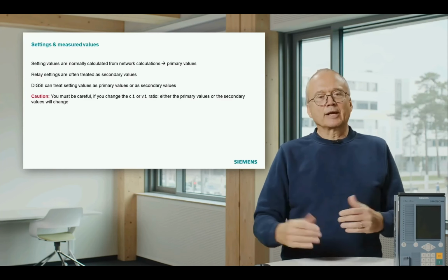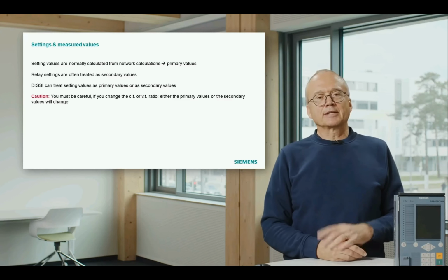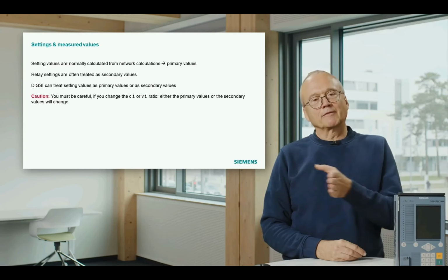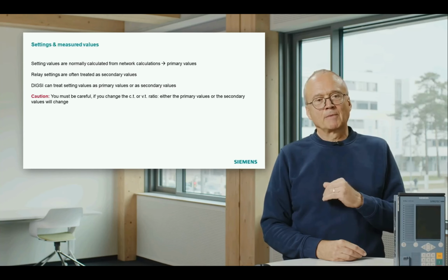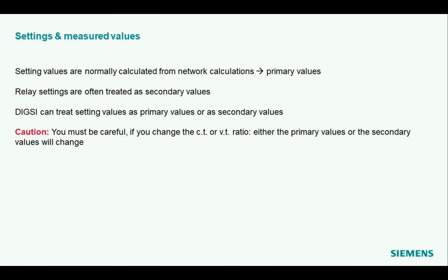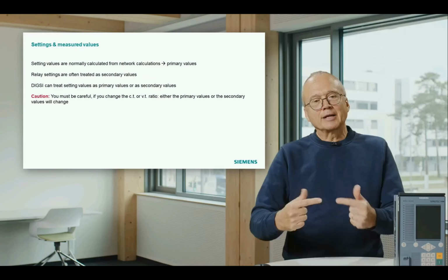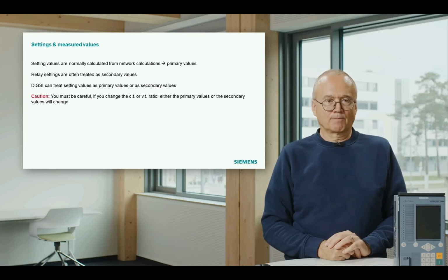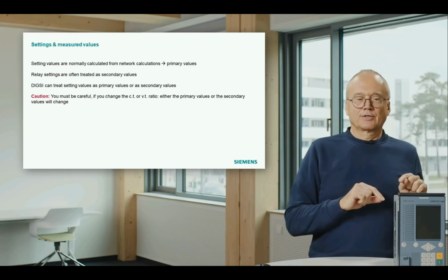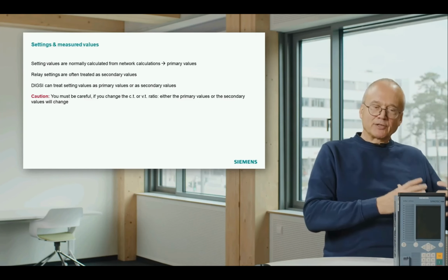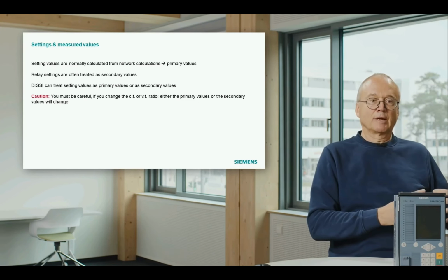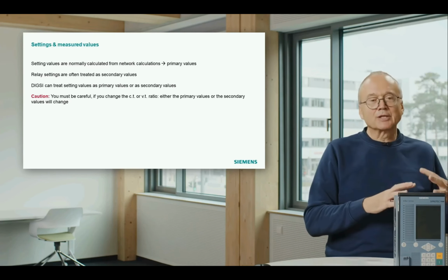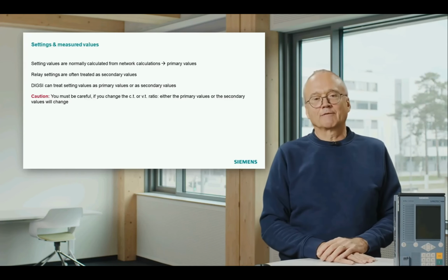In all states where you calculate settings or where you deal with settings, it must be clear, are you talking about primary values or secondary values of setting? Normally, you start the calculation of setting values from a network calculation. You have to calculate load flow, you have to calculate short circuits, and the values you see there are primary values. Relay settings, as the relay measures behind current transformer and voltage transformer, are traditionally often treated as secondary values.